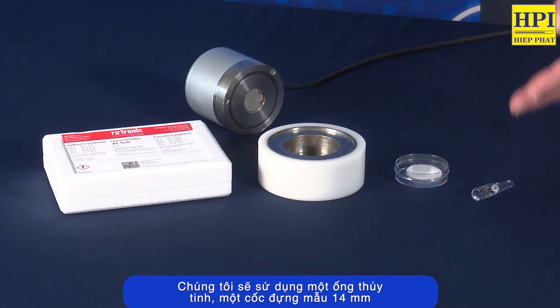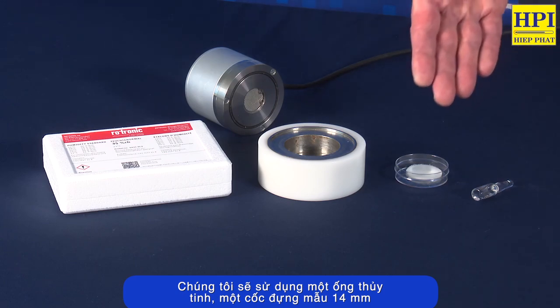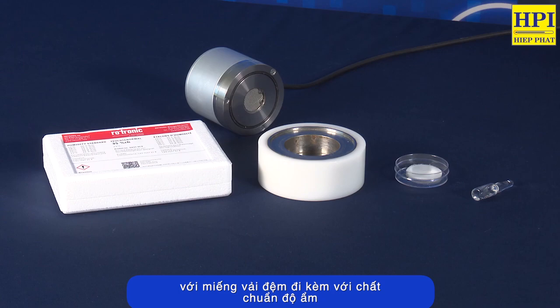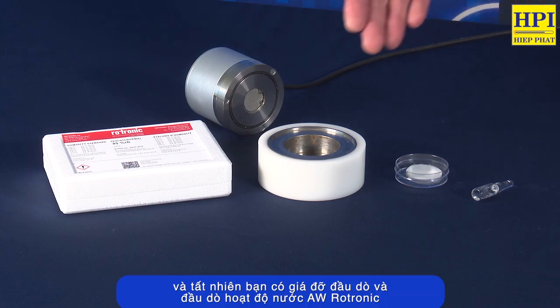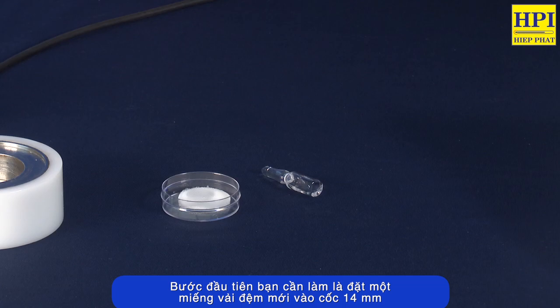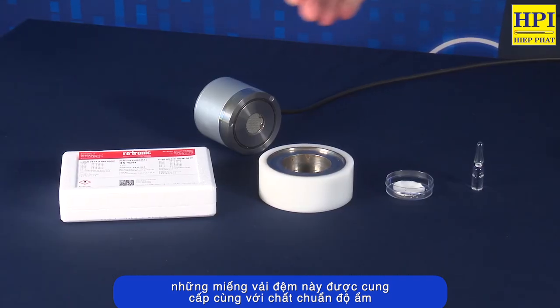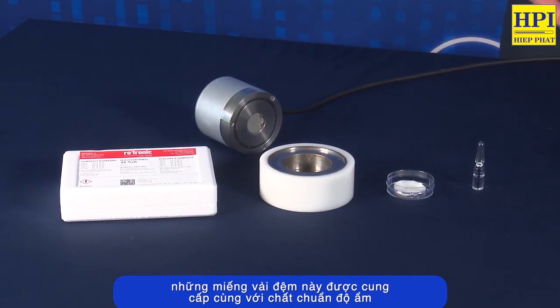We will select a glass ampule, a 14 millimeter sample cup with a fiber disc pad inserted, that comes with the humidity standard. And of course, you have your sample cup holder and the Rotronic AW water activity probe. The first step you're going to want to do is place a fresh fiber disc pad at the bottom of your 14 millimeter sample cup. These pads are provided with the humidity standard kit.